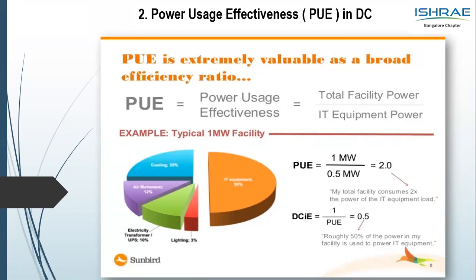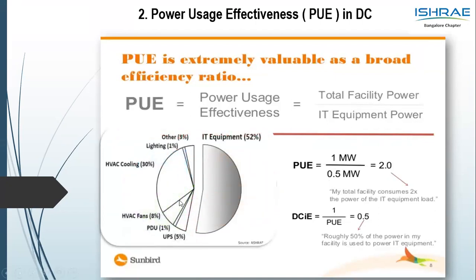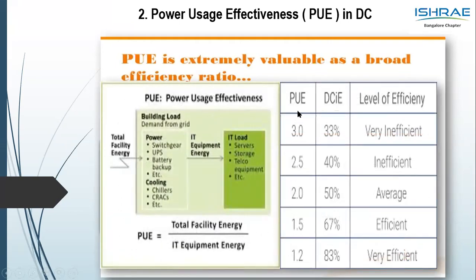We will look at those numbers in the coming slide. But the astonishing number is that in a PUE, the cooling per se takes away close to 30%. So the presentation is revolving around cooling. In the PUE of the data center, the cooling per se is 30%, which is a bigger chunk of it. As we get into the next slide, as I said, the PUE numbers range from 3 to 1.2, 3 being a very inefficient data center and 1.2 or below being a very efficient data center. So let's look at the worldwide numbers.